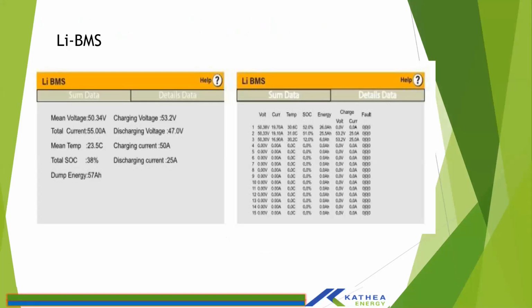Depending on the battery type, you would need to install an end of termination resistor, an RJ45 end terminator, to notify the inverter to say this is the last battery on the chain. So whenever I use a lithium, after connecting, you need to check your Li-BMS to see that you can actually read the battery voltage from the comms line. And the other thing that installers would encounter: you would actually read the battery voltage from the Li-BMS, but at the same time the inverter is giving a fault of low battery. So the low battery fault comes, the inverter will be detecting a low battery at its termination point.